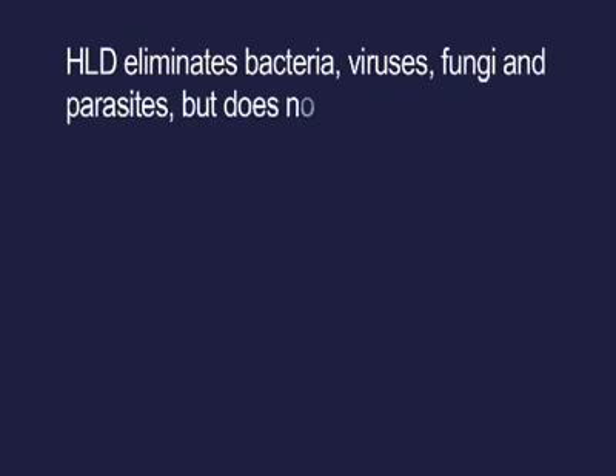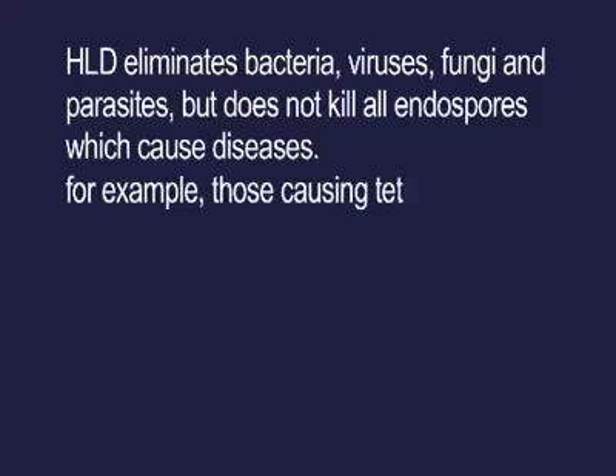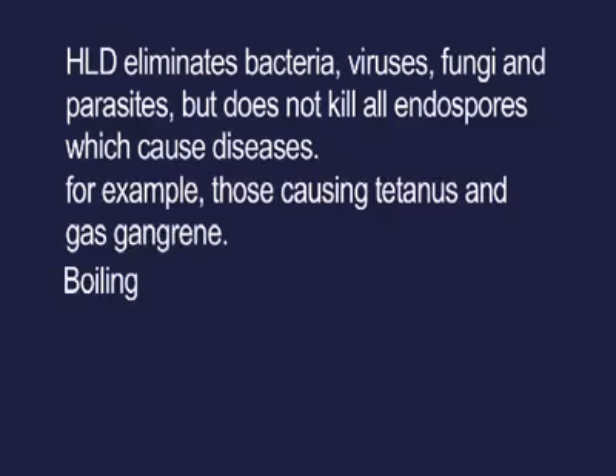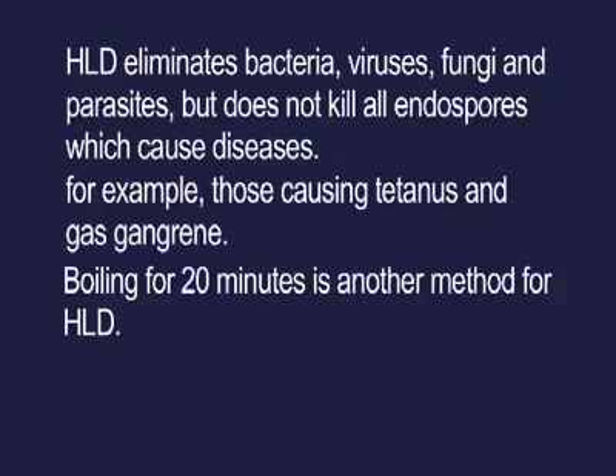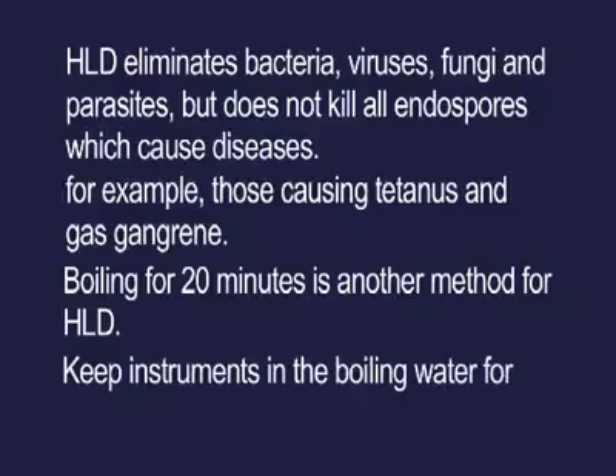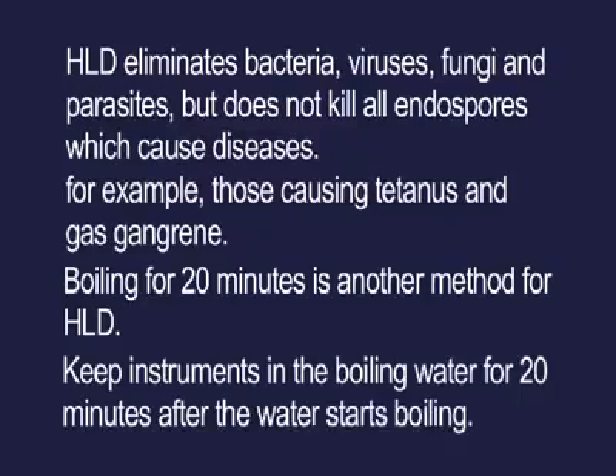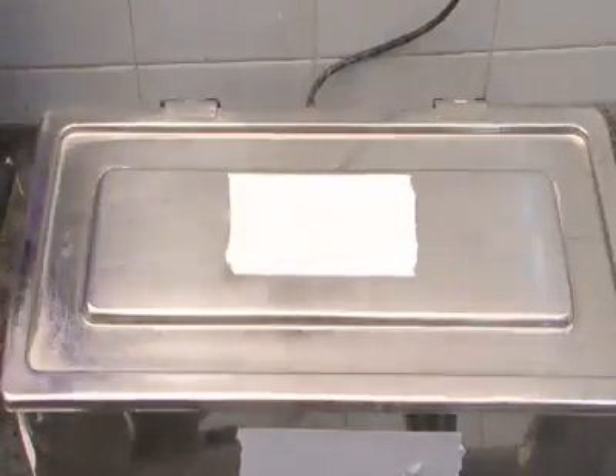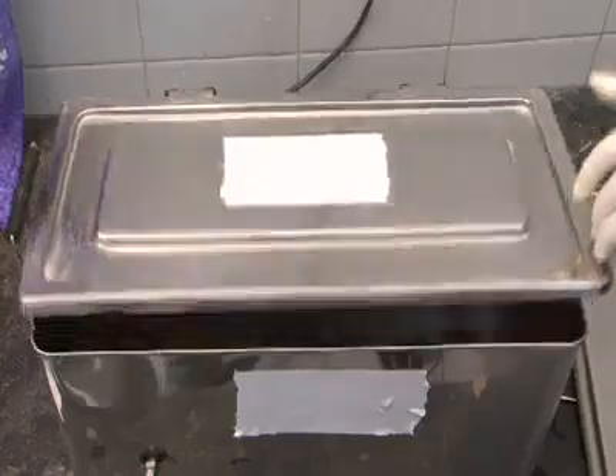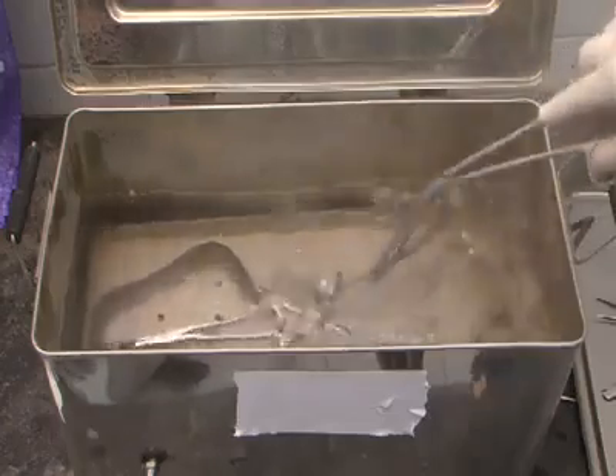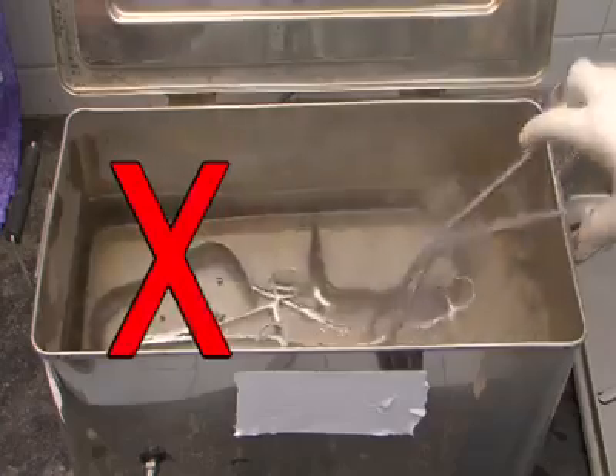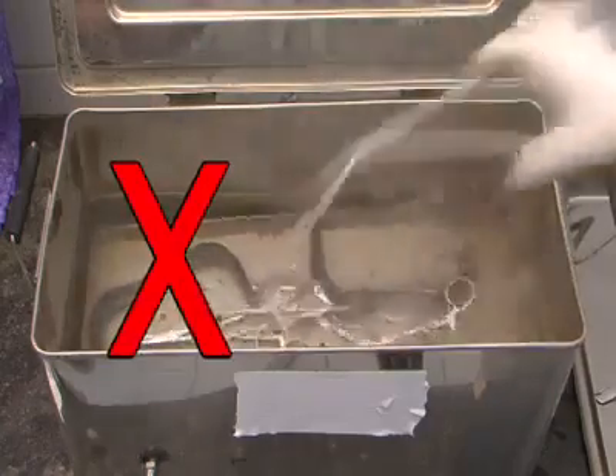HLD eliminates bacteria, viruses, fungi and parasites, but does not kill all endospores, which cause diseases, for example, those causing tetanus and gas gangrene. Boiling for 20 minutes is another method for HLD. Keep instruments in the boiling water for 20 minutes after the water starts boiling. Please ensure instruments are completely immersed in water. Lid of boiler should remain closed throughout these 20 minutes. Do not remove or add instruments or water during this period.